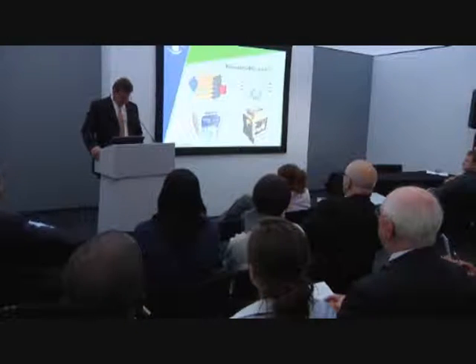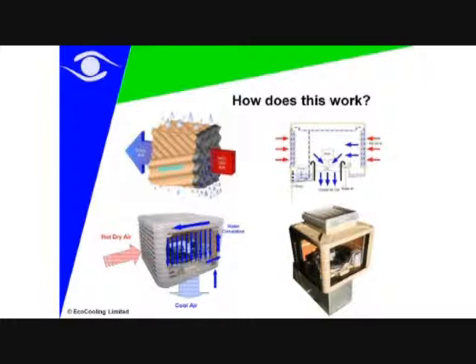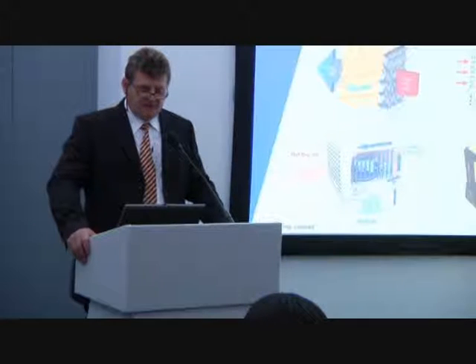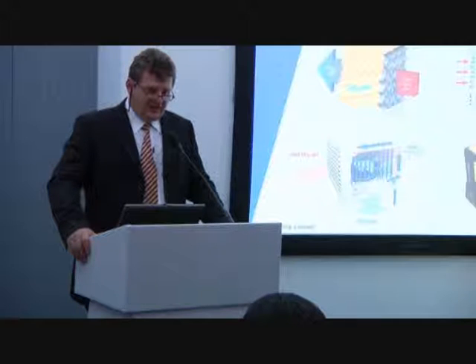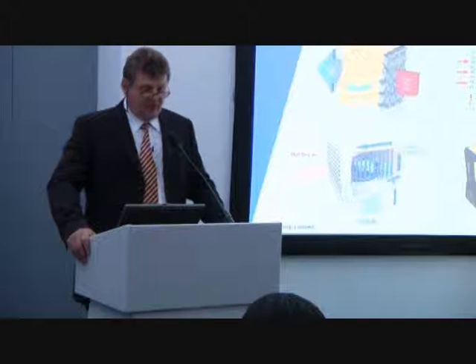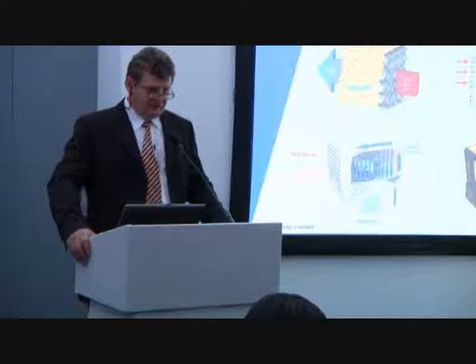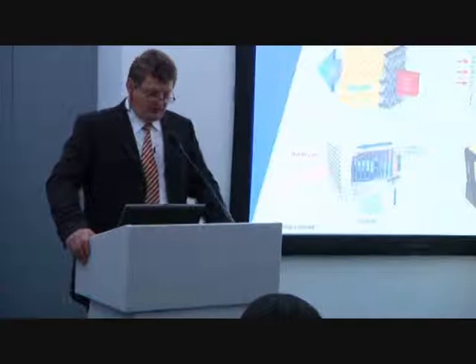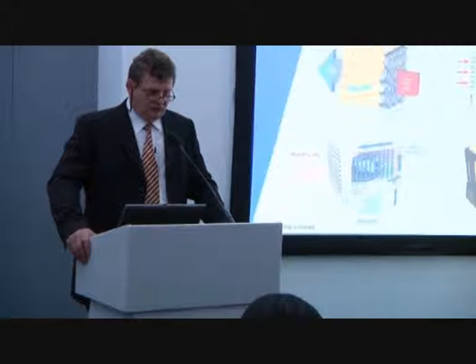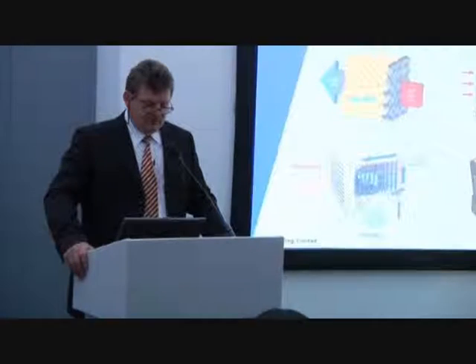How does it work? Well, it's no more complicated than air and water and their relationship. In the UK, when it is hot, the air is also low in relative humidity. And air is like a sponge. It loves to soak up water. If we put this air in contact with a wetted filter pad, water will evaporate into the air stream. The heat required to change the water from a liquid to a gas comes from the air, which then cools down. And we incorporate these wetted filter pads into a thing called an evaporative cooler, which is four wetted filter pads with a water circulation system and a fan to move the air around. And we build this into a device called a CREC, a computer room evaporative cooler.